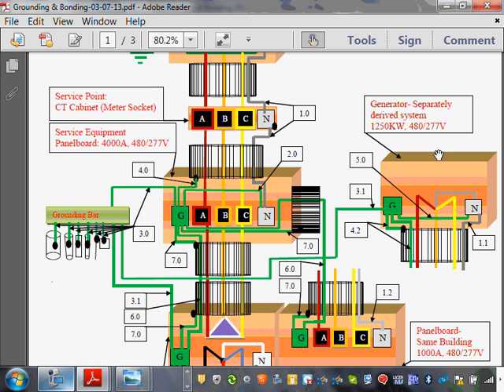Now when you run a separately derived system for a generator, the first thing you need to do for the generator is take a grounding conductor and tie it to the grounding electrode system inside your building. If it's outdoors, you can drive a ground rod here and tie it to the ground rod, and it will be bonded to the system through the supply-side bonding jumper right in here. So let's size this first, or maybe size the neutral first. I have a neutral coming out of this generator, and I need to size that neutral, right? So let's go to 1.1 first and size that one.